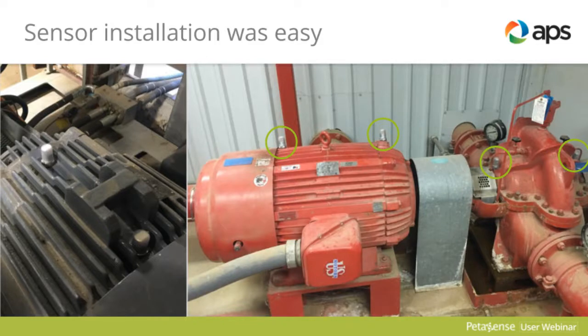Well, the sensor installation is very easy. In most cases, your equipment doesn't have to be shut down or locked out for the installation. If you take a regular vibration reading with a portable route, it's basically the same way that you're doing. What I have is a small Dremel tool with an acorn grinding tool on it. You need to clean the paint off or get it down to bare metal at about a 1.5 inch diameter circle. And at that point, you can epoxy it in place.